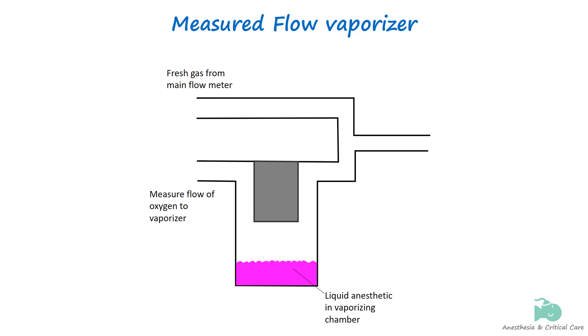Another method of regulating vaporizer output is the measured flow method. This method is used in older types of anesthetic vaporizers. It involves a vaporizing chamber where an anesthetic agent is heated at a temperature above its boiling point. A measured flow of oxygen is allowed to pass to the vaporizing chamber, which carries anesthetic vapor at a very high concentration.